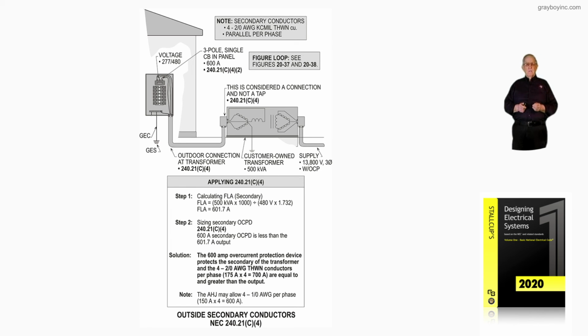Now, the note says the authority having jurisdiction may allow 4 1-aughts, and 4 1-aughts would give you 600 amps exactly. So again, it's always wise to check with the authority having jurisdiction or the plan checker of a particular state, county, or city, and see exactly what they are going to require when you have an installation of an outside transformer, making an outside transformer secondary conductor tap in accordance with NEC 240.21(C)(4).